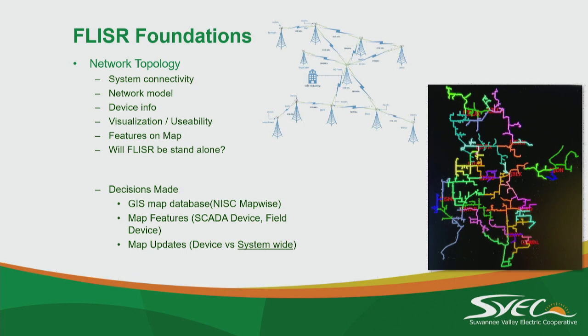It gives you a very quick visual. Everything's colored by feeder. When something goes out, if this feeder in green goes out, it flashes white. If it backfeeds a portion of it, this turns yellow, this turns pink, and let's say this part here is still flashing white. In our control room, you quickly know flashing white is bad, and you can look and see where it's fed to, where it's open. It gives you a very quick identification of what's happening.